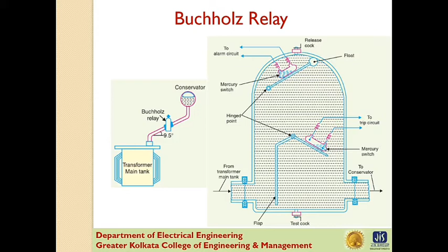Now, if a serious fault occurs in the transformer, an enormous amount of gas is generated in the main tank, and oil from the main tank rushes towards the conservator via the Buchholz relay, and in doing so tilts the flap to close the contacts of the mercury switch. This completes the trip circuit to open the circuit breaker controlling the transformer.